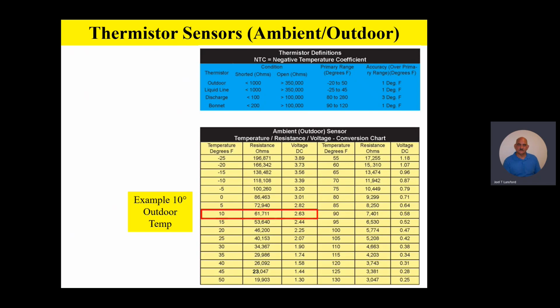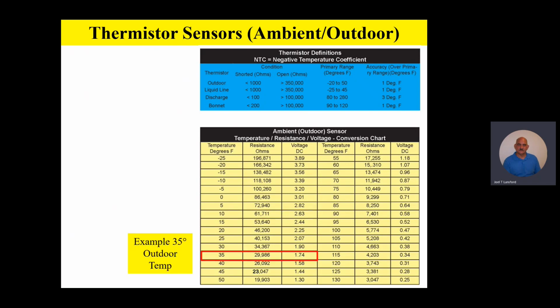Let's do another example. Let's say we're looking at, again, an ambient or outdoor temperature sensor, the one that just kind of hangs down below the control panel. This is the ambient or the outdoor sensor. Let's say it's 35 degrees outside. If I know it's 35 degrees outside because I measured my outdoor air temperature, and I remove the sensor from the board, and I take my ohm meter and I read the ohms or the resistance of that sensor at 35 degrees outside, it should read 29,986 ohms with it unplugged off the board.